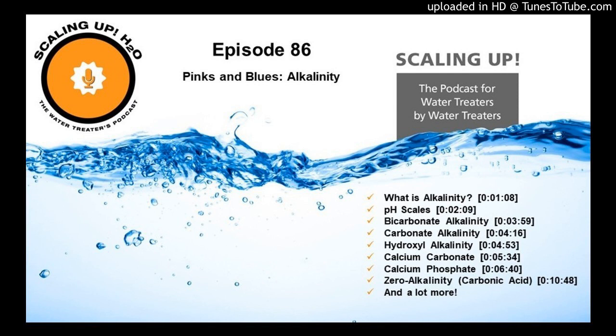All right, so let's move down the scale, and now we're at 8.3 to 4.3. Well, that's our bicarbonate alkalinity. And bi is our big fancy chemistry term that just means hydrogen. Well, that is between 8.3 and 4.3, and we might also call that M alkalinity. That M comes from an older reagent, one that our fathers might have been using, or my father did use, and it was methyl orange. And it wasn't a great color change. I think it went from like a red orange to a yellow orange. It wasn't a very definite one.